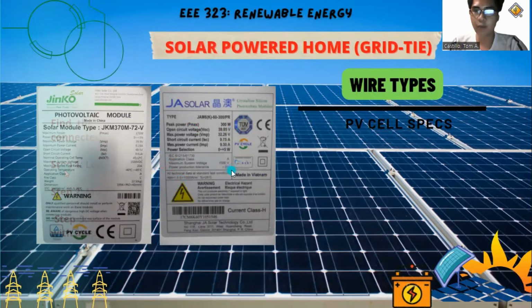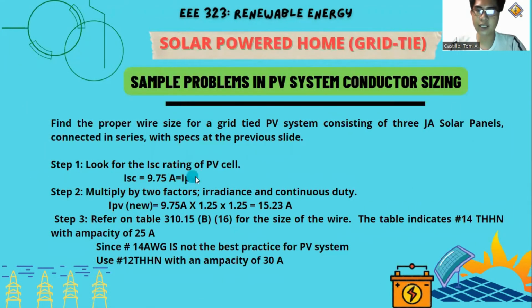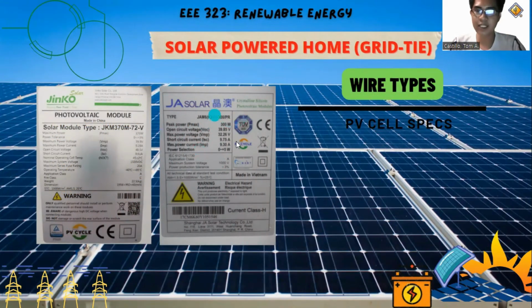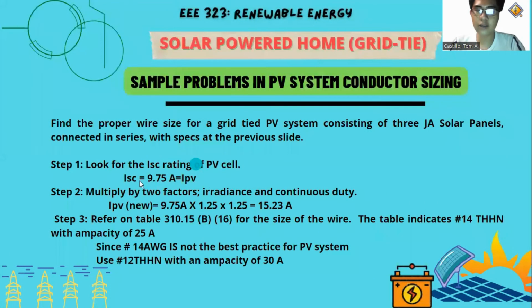So doon na tayo sa step 1. Step 1, look for the ISC rating of the PV cell. So base sa specs dito, ang ISC is 9.75 amperes. So ang current natin is 9.75 amperes. Siya yung IPV. So doon na tayo sa next step. Ang next step is multiply by 2 factors. Ito yung irradiance and continuous duty. So bali current natin, which is 9.75, times natin sa 1.25 times 1.25. So ang IPV new natin is 15.23 amperes. So, ito na yung new current na mag-generate.